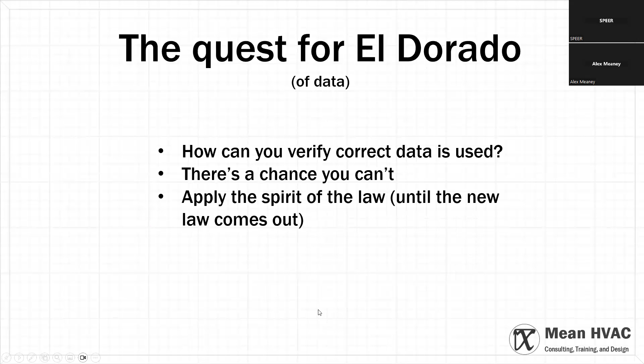The rules are fairly straightforward. You always need to have enough latent capacity. That should be 100% or higher. You want to have enough sensible capacity, but it's okay if you're low. You're actually technically allowed to be under by 10%.